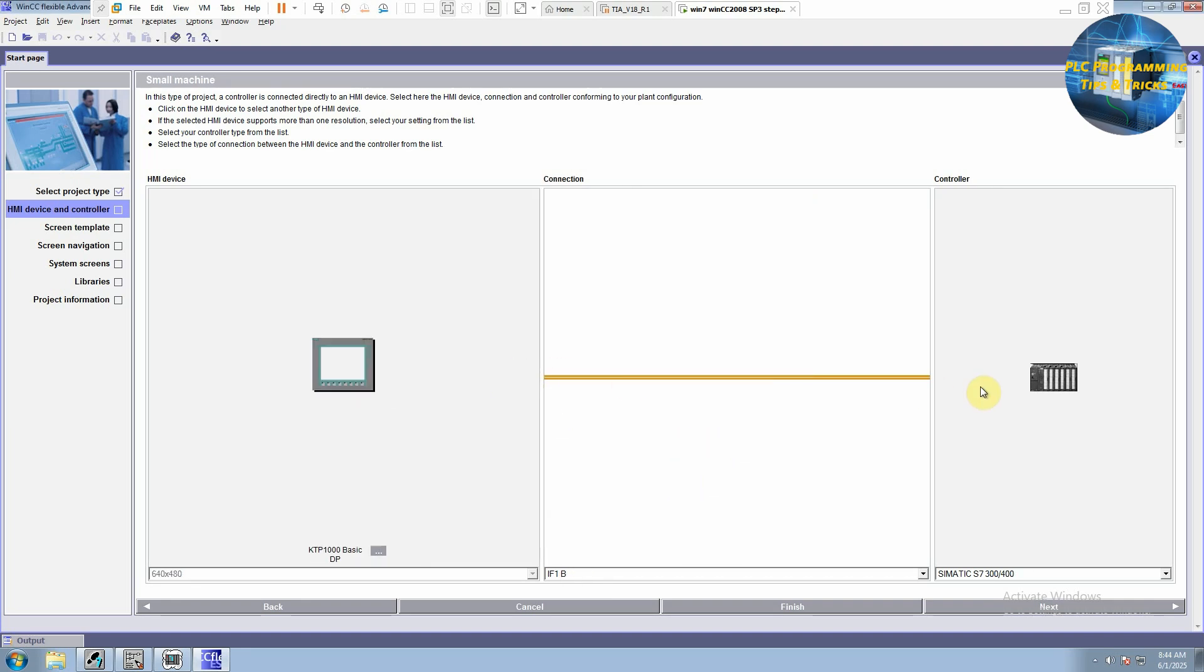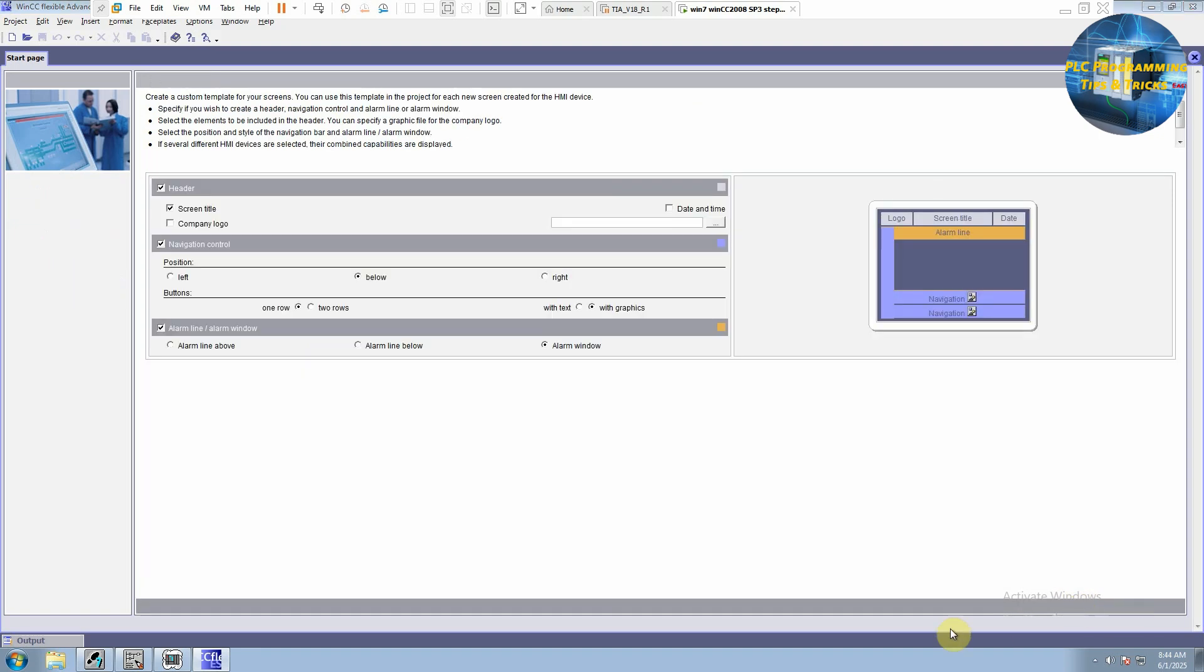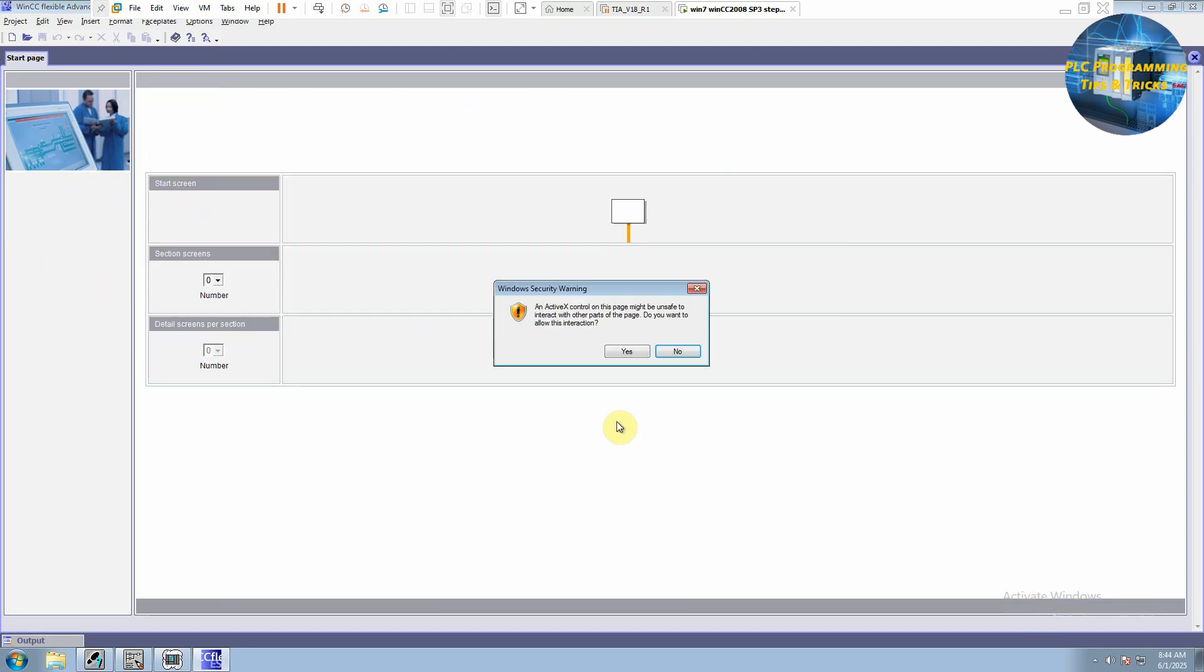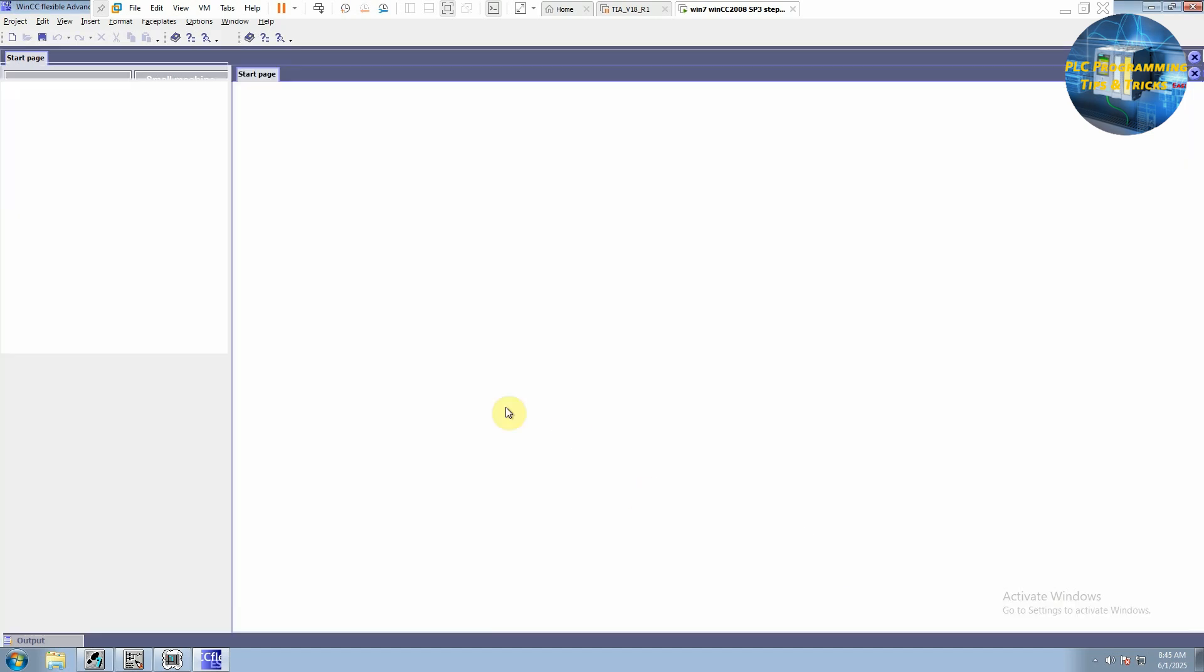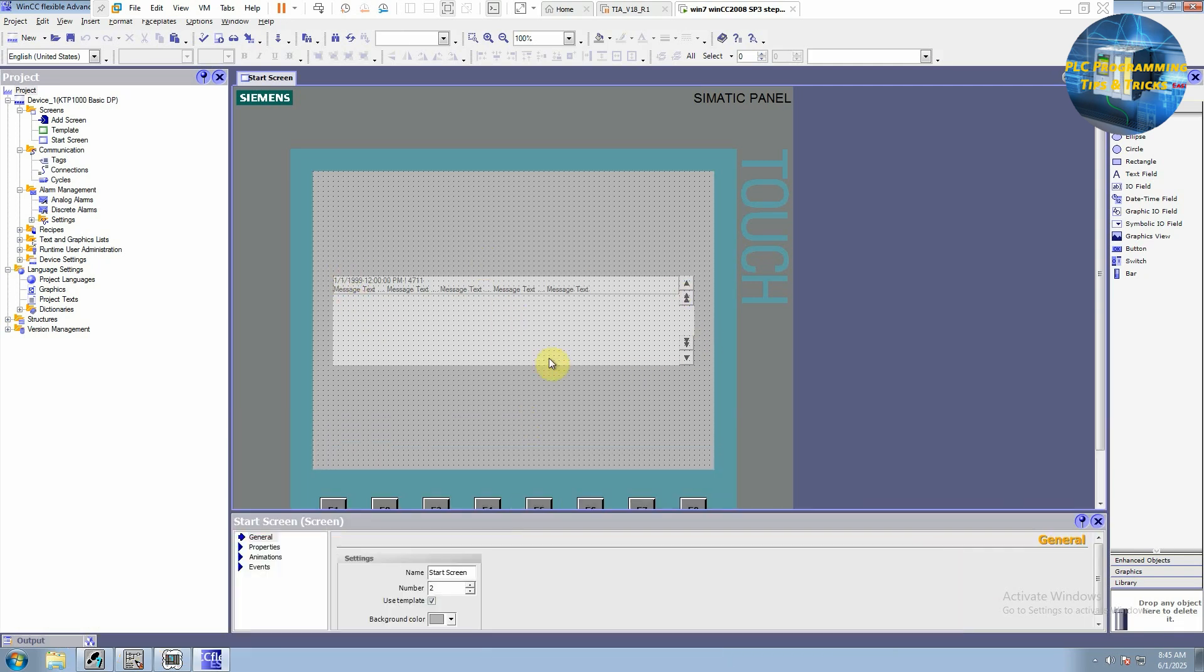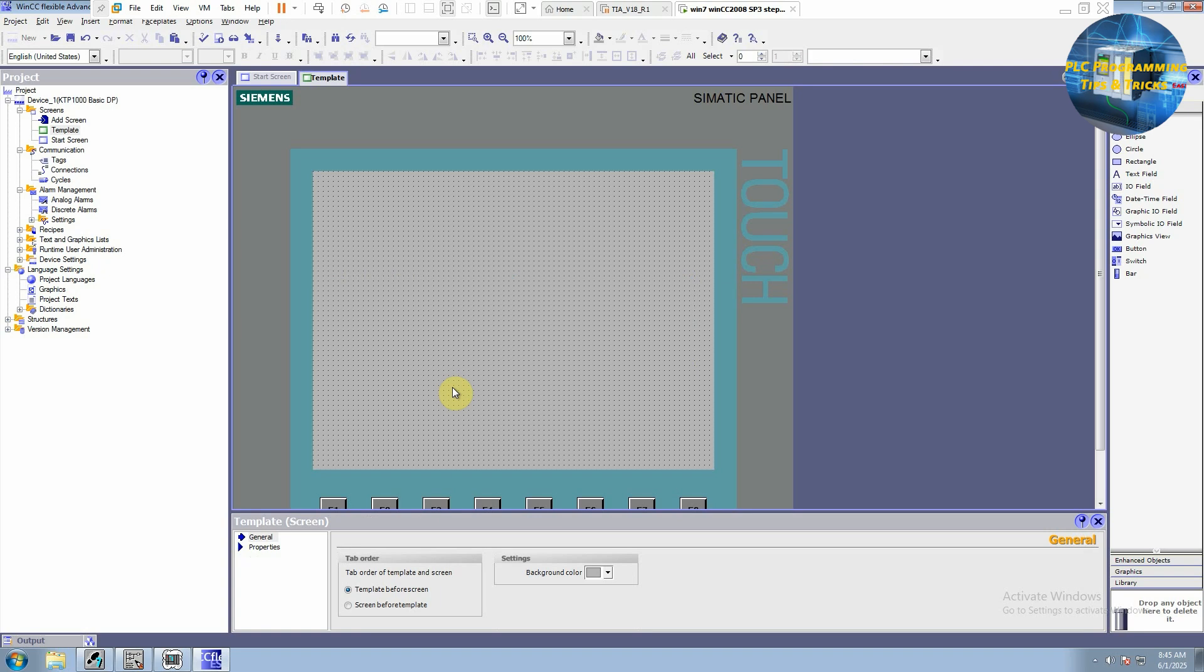And this HMI will be connected to this S7-300 or S7-400 PLC via MPI-DP protocol. Next, we will disable the default settings. Header and alarm window we don't need for now. We will click on this finish button. Now this is the start screen for the HMI and it already is showing some alarm window. Now to disable this one, we will go to the template and delete this screen.